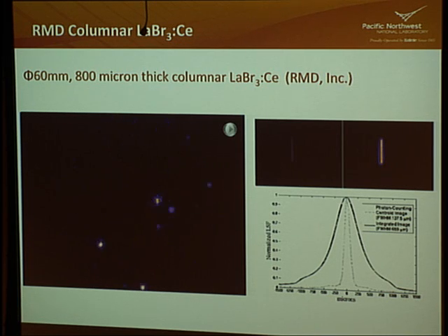You can get very high spatial resolution with this detector if you identify and estimate the interaction of each individual gamma ray photon. So of these two images shown here, the first one on the left is where we've identified each gamma ray photon and estimated where it interacted in the crystal, whereas on the right we've just taken all the light that's produced, haven't identified each individual one, and summed it up. Here you can see the two cross sections, the profile of those. So if we estimate each interaction, we can get much higher spatial resolution. That's really a key concept with this detector technology: if you identify and estimate each detection, you can get very high spatial resolution.